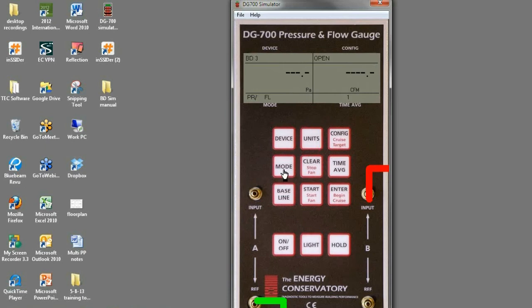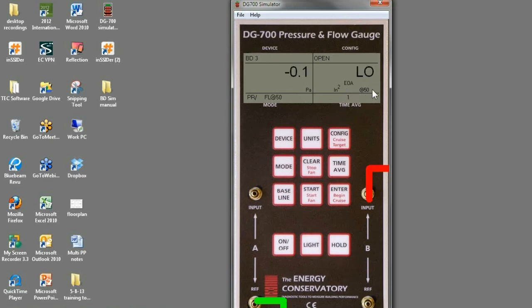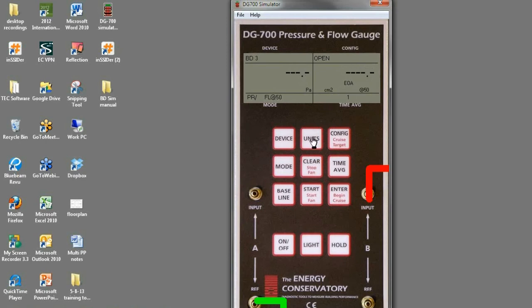If you're in the pressure flow at 50 mode, you can get meters cubed per hour at 50, liters per second at 50, or inches squared equivalent opening area at 50. So if you want to know how big of an equivalent opening there is, using the EOA method at 50, it'll display what that is. Once you get above 10 pascals, it'll display the leakage area. So that's units.